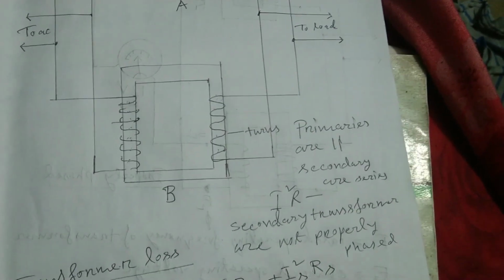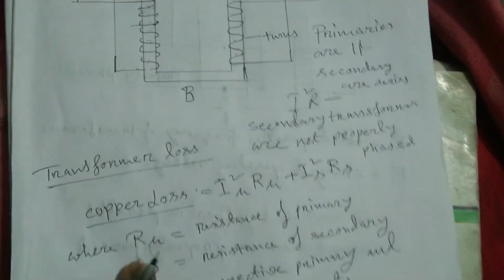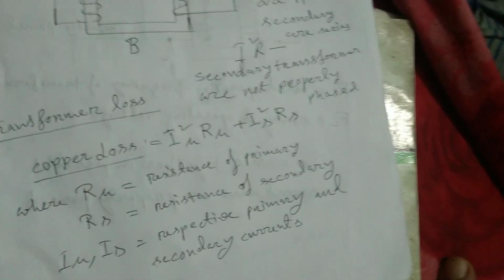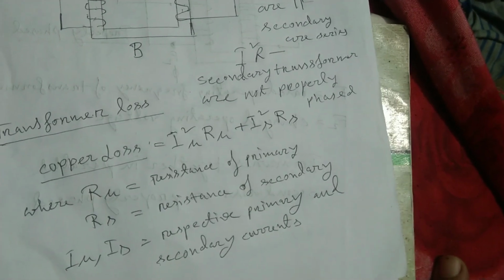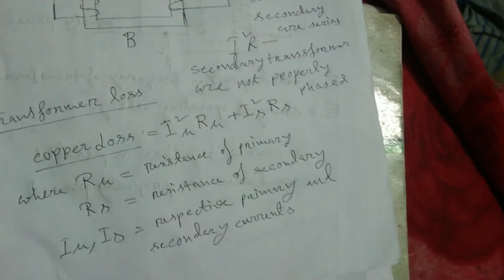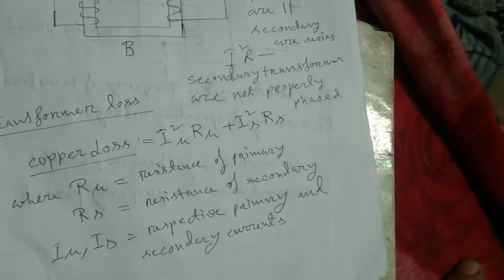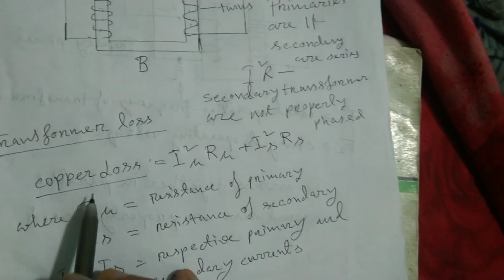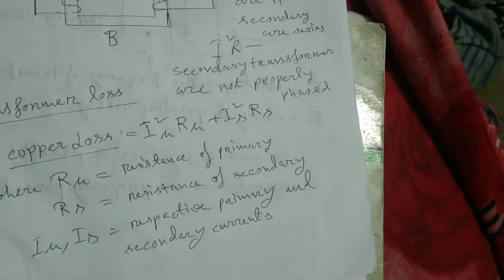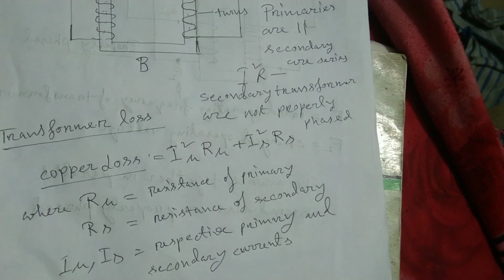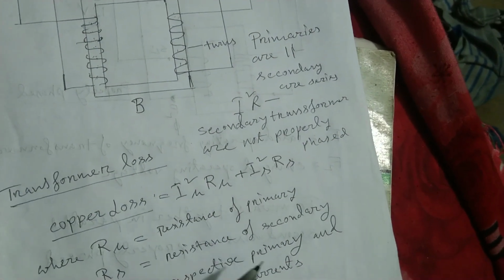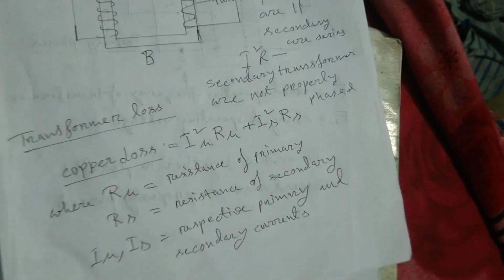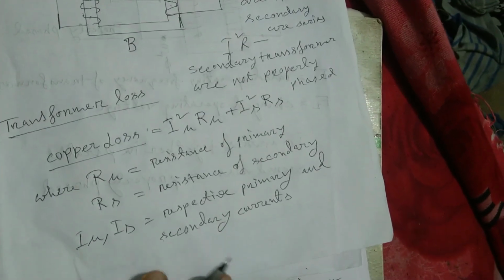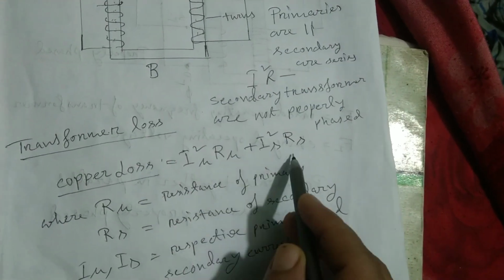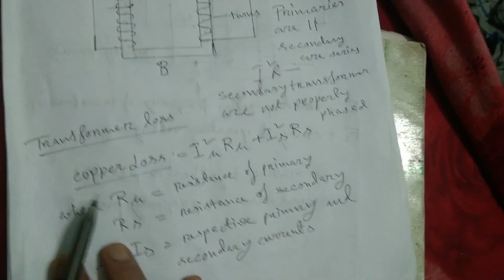Now transformer losses. Power losses in the transformer occur in the transformer core material and in the transformer primary and secondary windings. So there is eddy current loss. I think that you know eddy current, otherwise I will discuss it in my channel. There is a formula for the copper loss. Copper loss is the power lost in the primary and secondary windings of the transformer, due to the ohmic resistance of the windings. The formula is copper loss equals Ip squared Rp plus Is squared Rs. This is the total formula.